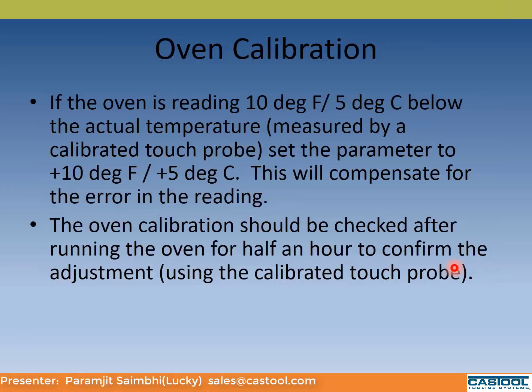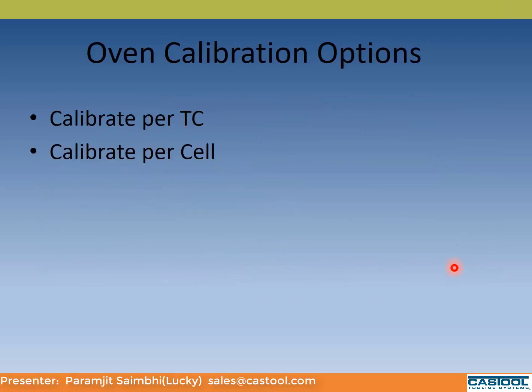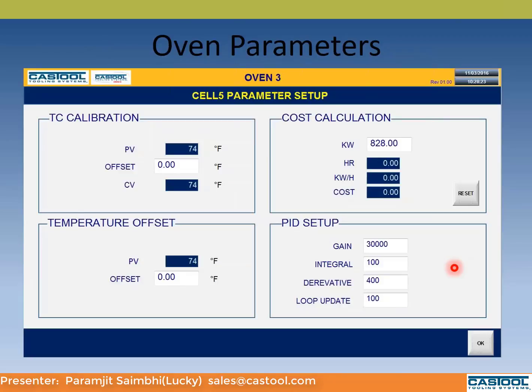We calibrate each oven. You can calibrate per thermocouple or per oven cavity. You can create an offset. So our software gives a very user-friendly interface for calibration, because a lot of plants do hire third-party companies to come in and calibrate the equipment, I think once a year or something like that, according to whatever standards they've set up. So it is possible to do calibration right on our master controllers. Here's a screen showing you how to calibrate a thermocouple. And here we're showing you how to calibrate just the cell.